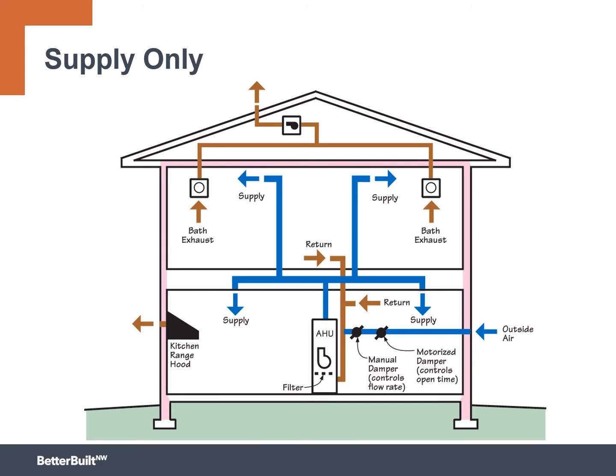Again, we're going to go through some examples, but the math would tell me that I have to multiply my base ventilation rate by 1.25 if I'm not balanced, but I am distributed. Whereas if I'm neither, I have to multiply it by 1.5. You can start to see some of the choices. The other benefit here is, you can put this outside air intake where you choose. You as a builder get to choose where that is. So you can choose better indoor air quality locations, right? To make sure that people know where their fresh air is coming from. That's a pretty nice benefit. So supply only does have some nice benefits to it. It has some challenges as well, and we'll get into those in just a second.